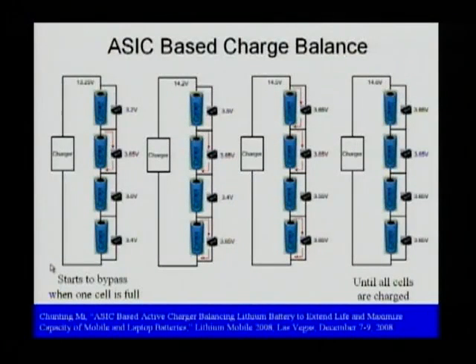A second thing we've developed is a balancing IC that can balance the batteries during charge. The diagram shows four battery cells in series, each with an IC in parallel with the battery. The IC is a smart device that can automatically turn on when the battery voltage reaches a certain level. In this design, we use iron phosphate batteries, so the IC is set at 3.65 volts.